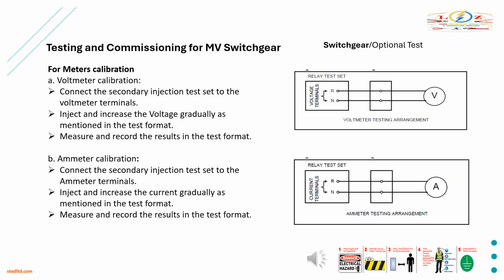For meters calibration. For voltmeter calibration, connect the secondary injection test set to the voltmeter terminals. Inject and increase the voltage gradually. 1. From 0 to 25%, 50%, 75% and 100% of the full-scale voltage of the voltmeter. 2. Record the corresponding voltmeter readings. 3. Inject 100% of the normal voltage and record the corresponding voltmeter reading on the test record sheet.